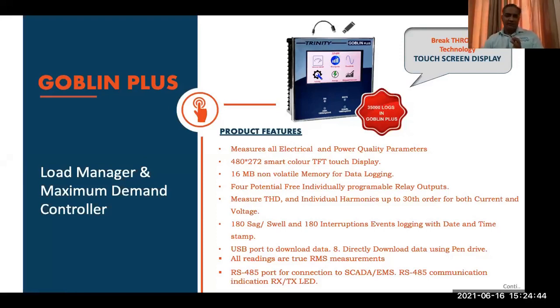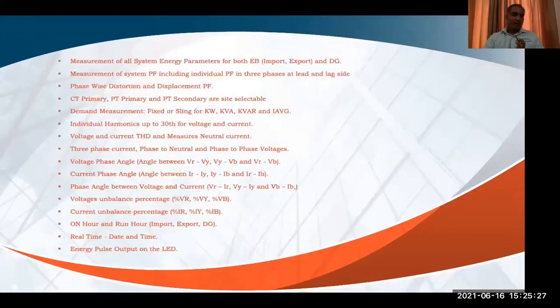The meter has 16 MB non-volatile memory. It is expandable also on user request. The moment we switch on this meter, it will start recording all your electrical parameters: all voltages, all currents, all energies, all power, all harmonics up to 30th level, all sag events, all swell events, all interruptions, all demands, everything will be recorded in the meter's memory. Up to 35,000 logs can be recorded. The minimum log duration is 1 minute and the maximum log duration is 60 minutes. And the moment we put our pen drive to the meter, everything gets transferred to the pen drive itself. And above this, it has dual source measurement and it has 4 relay contacts as well.